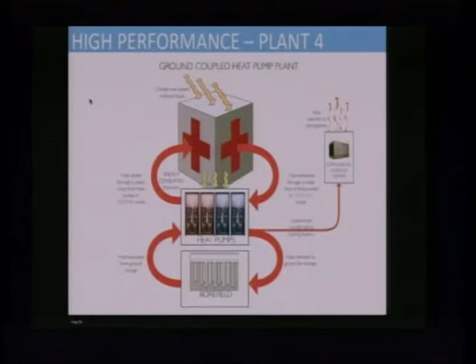An important part of this is that we actually made a change after one of our peer review meetings. We had the bore field sized to the peak load, which means you have a lot more bores, and the bores are really expensive. We made the decision to not size it on the peak, but size it on the base load, and then have peaking - not represented here - a peaking chiller and a peaking boiler, so we could have a smaller bore field, less expensive, but still efficient.